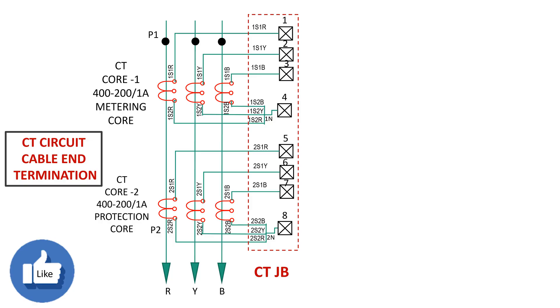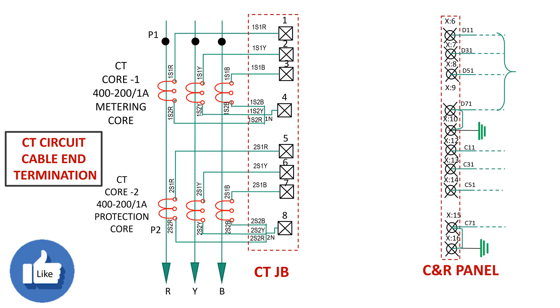We see the drawing of 33kV CT connections having one metering core and one protection core. At the CT end, all current transformers are wired according to the marking of secondary terminals, and wires are brought to a junction box and terminated at terminal block numbers 1 through 8. On the other side, at the control and relay panel, metering as well as protection wires — such as D11, D31, D51, D71, C11, C31, C51, and C71 — are brought to terminal blocks X6, X7, X8, etc.